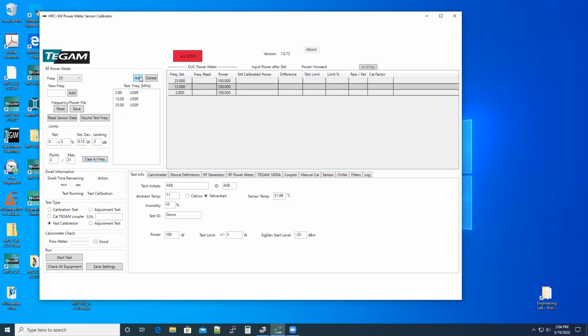Now there's 2 kinds of tests we can do on this sensor. We can calibrate it or we can adjust it. And we'll go ahead and adjust this sensor today. I'll go from the fast calibration button, click the adjustment test button, and the main difference that does is it illuminates these check marks over here for burn, which is essentially program the EEPROM in the sensor.